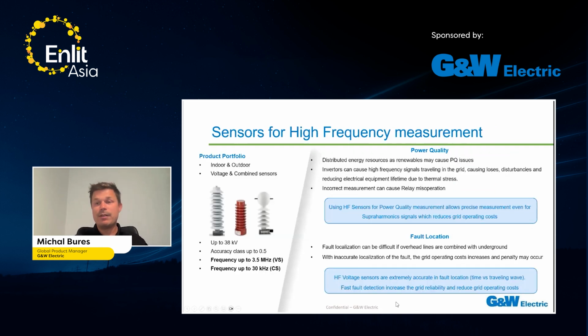But don't worry, there is always a solution. As we already know, the combination of capacitive dividers and the active sensor can do great things. One of the things is power quality measurement, where we can measure the supraharmonic signals precisely. The portfolio on the left is just a portion of the portfolio, but this specific one we already use for high frequency measurement. The voltage level is up to 38 kV, with a standard accuracy up to 0.5. As I said, we can go even into more precise ranges. The frequency range is up to 3.5 megahertz for the voltage sensors and up to 30 kilohertz for the current sensors.